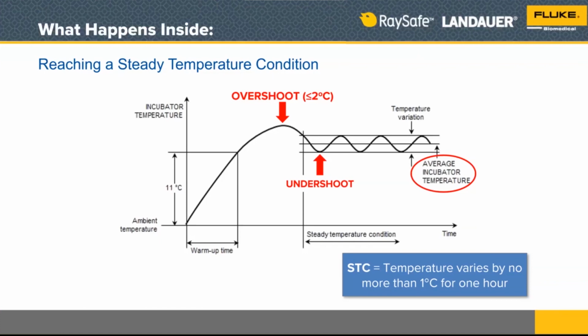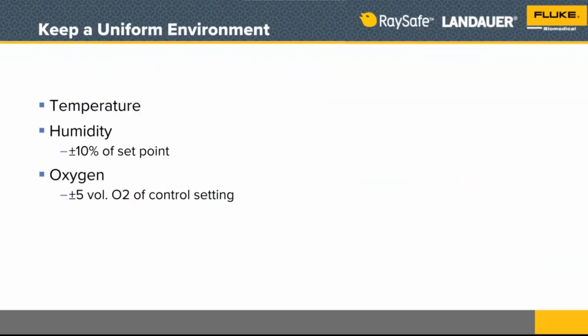Right? And these tests come from the international standard for infant incubators. I think we'll specify exactly what that standard number is. It's under the umbrella of the IEC 60601. So we'll get to that. So this is kind of what we're looking for, that warm-up time. Then at the finish, we're looking for that stable temperature, the STC.